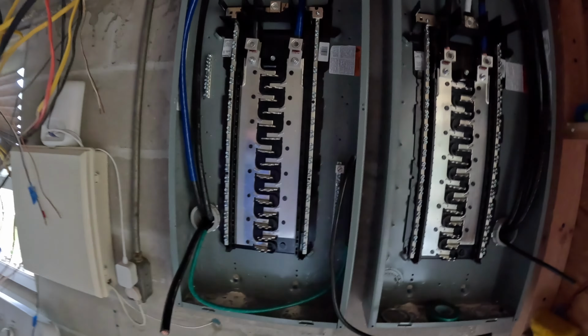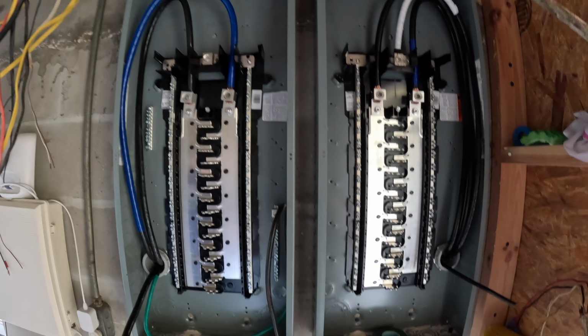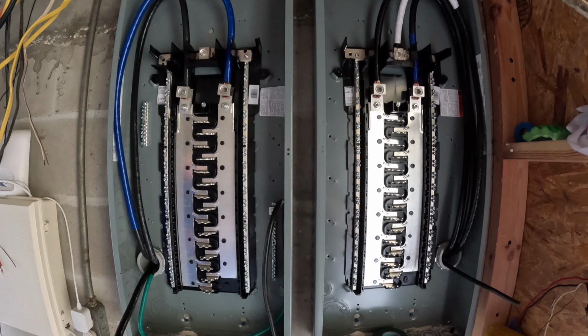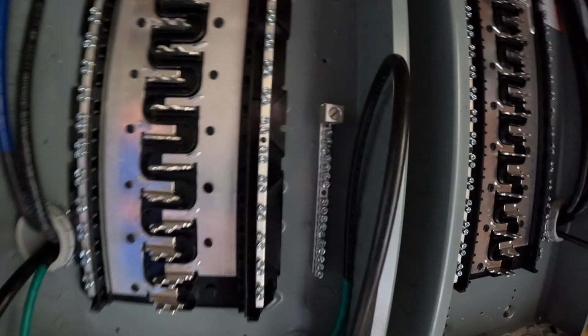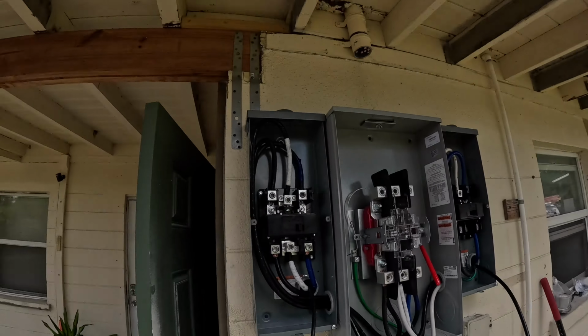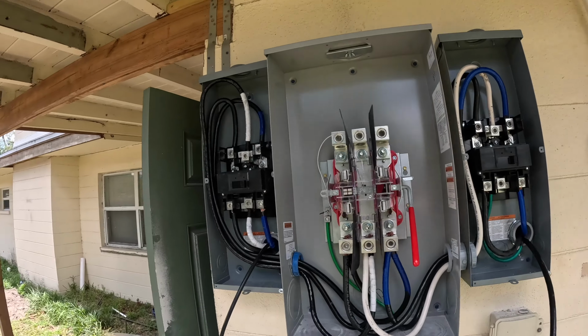These are technically considered sub panels because the main emergency disconnects are outside, and that's where the main bonding between ground and neutral is. So they're installing separated grounds - separated grounding bus bars, so that's where the grounds will land on the panels on the inside, because you can only have one bond between neutral and ground in a subsystem, and that's happening at these exterior disconnects here.